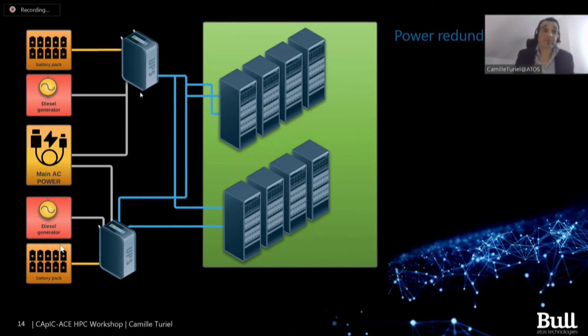For a Sequana rack, to give you an idea, with 1 kilowatt per blade, that's 96 kilowatts per rack. If you have a few racks, imagine how big the power draw becomes. It's a big challenge to store that. So the idea is to have the UPS as a buffer, which triggers the diesel generator to start as soon as possible, generally within 1 or 2 minutes. Then the generator takes over from the UPS and provides power directly to the nodes.